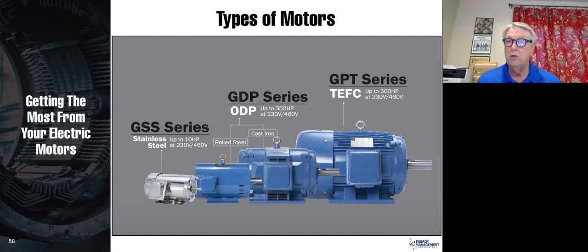Now, still in this case, the air is going through the motor, so the interior of the motor is going to get dirty. So the workhorse of American industry is the totally enclosed fan-cooled motor. You want a cast iron frame so that it's very stiff and holds the bearings in alignment, but the air in here, as we showed you earlier, does not go through the motor. It comes in through the end bell. The fan blows it over the outside of the motor, and so this motor will be very clean. I come from the steel industry. I can tell you lots of motors where you weren't sure a motor was there because of the dust and dirt and grime, and yet it was still running. Not saying that's a good idea to treat motors like that, but that's why we buy this TEFC.